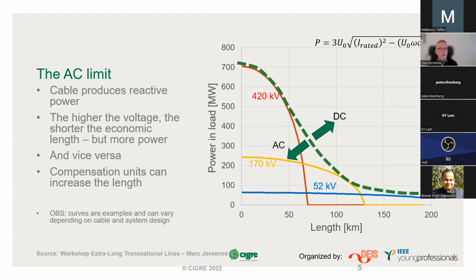So why not use those? The simple answer, probably known to all of you: cables, being a concentric structure, produce their own reactive power. And if such a device produces reactive power, a current will flow through the conductor, occupying it with current that can no longer be used by the useful current you actually want to transmit and use at the other end of the cable.